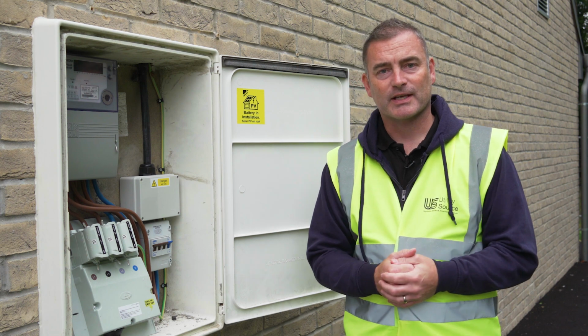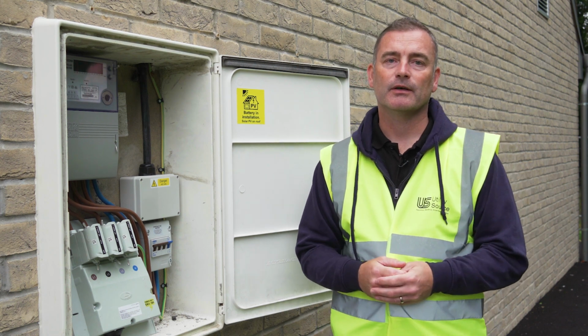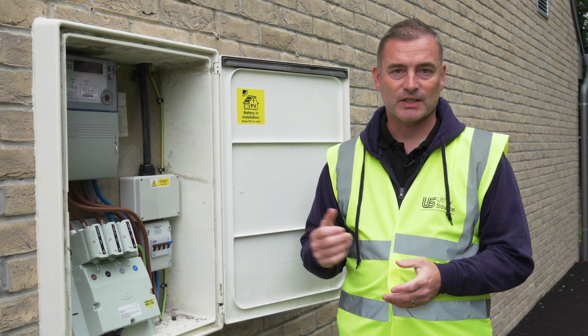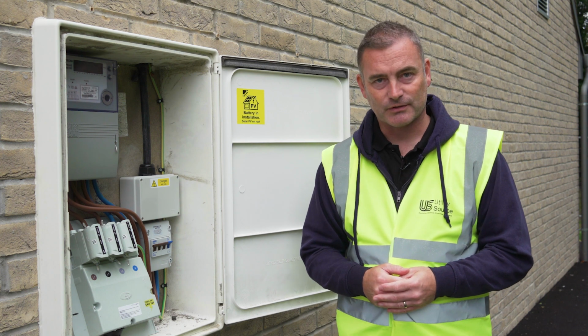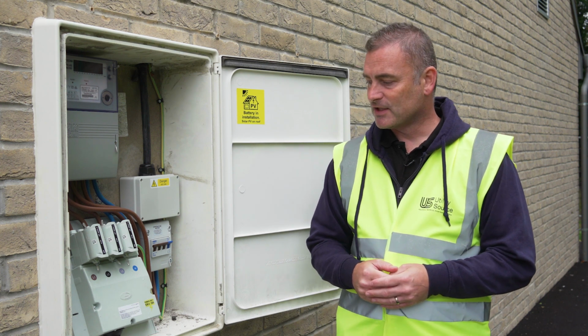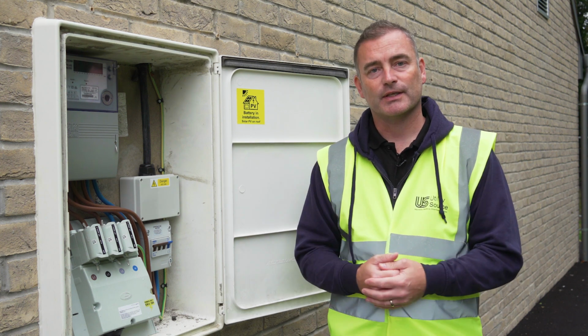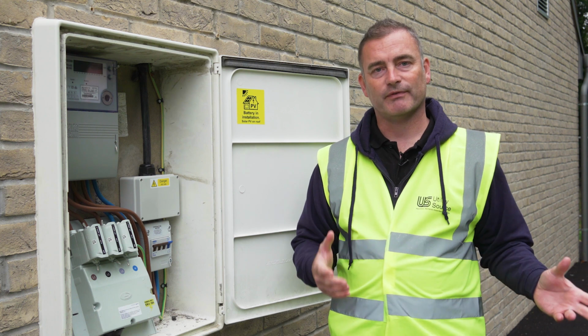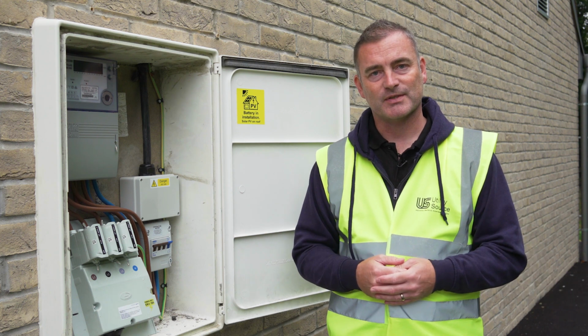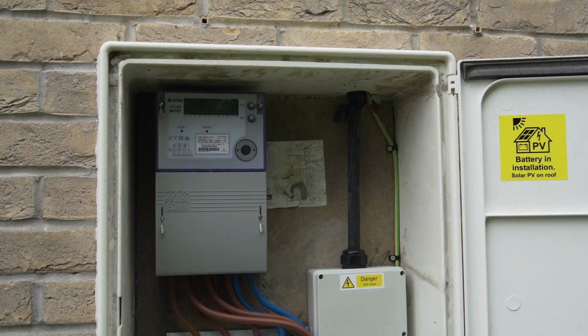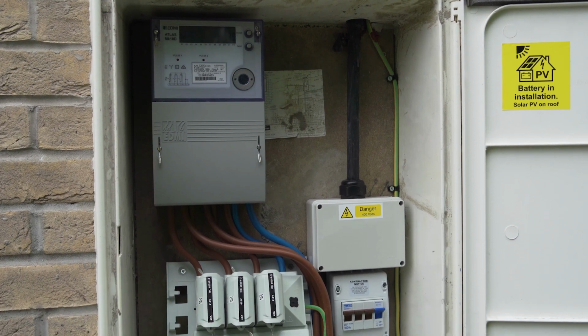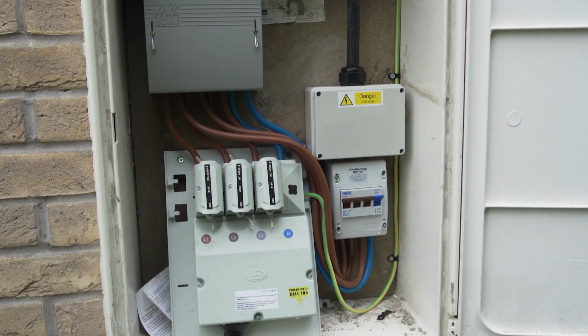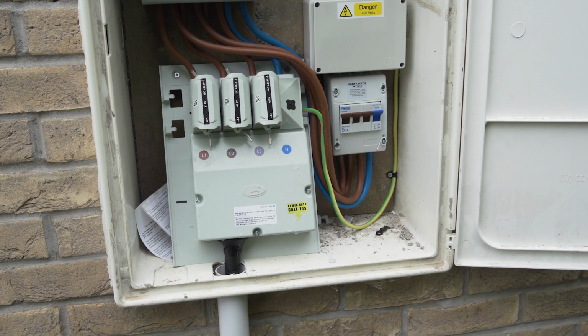Our biggest challenge at this café project was the installation of the electric supply. You'll see that we've installed a three-phase electrical service, and the challenge wasn't actually around the installation, it was around the load that was available to allocate to the property. This kind of unit with 80 amp fuses in gives around 55 kVA for the building to operate with.